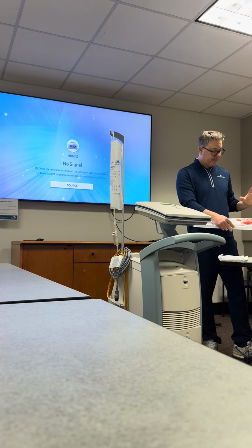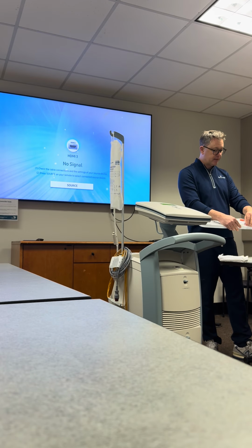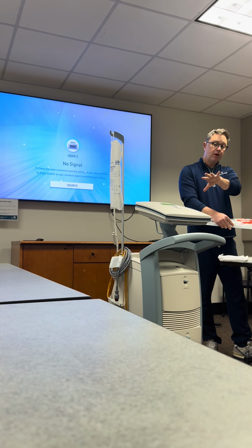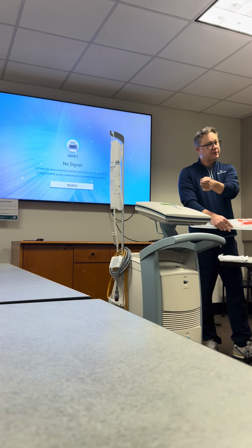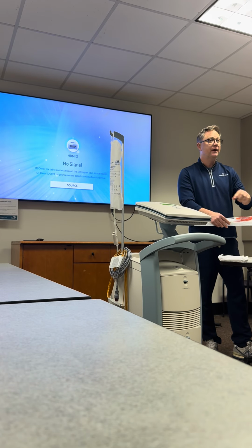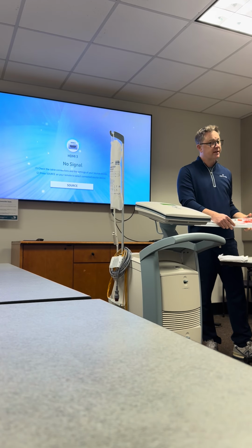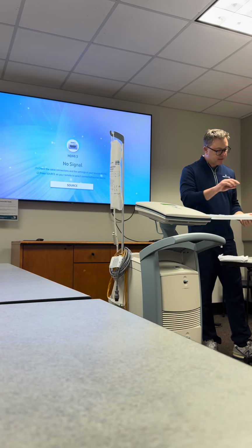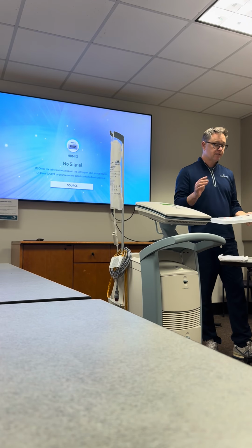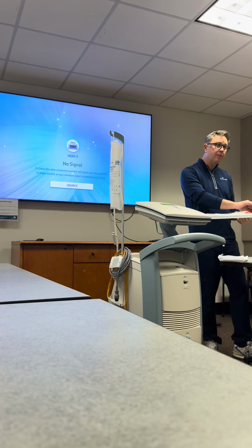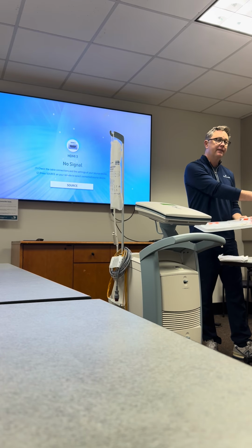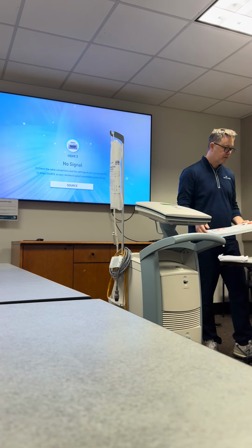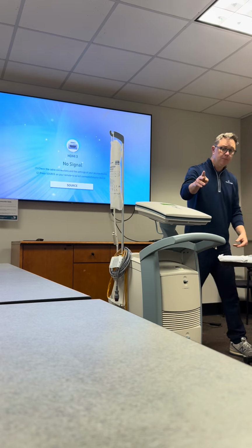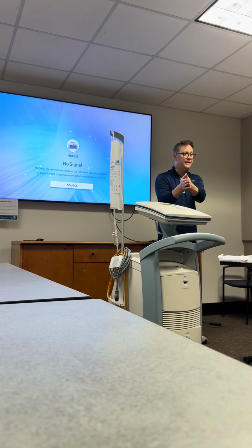So if something were to happen here, like this fiber optic cable were to break, you get a fiber optic sensor alarm, you would simply unplug it, and then you'd have to zero out your standard pressure bag. So it keeps the line patent, and it's just a backup source. If you were using a non-fiber optic balloon, again, that would be your primary source to get your arterial pressure waveform. So balloon pump, when you hit start, is going to look for the EKG.